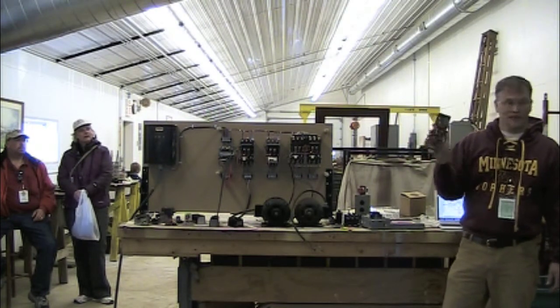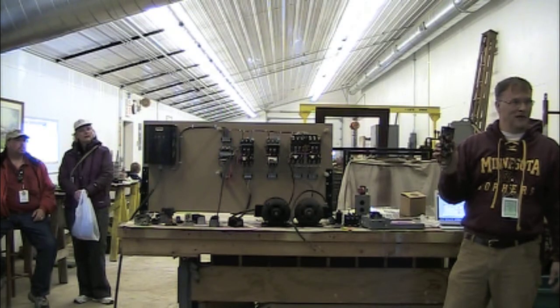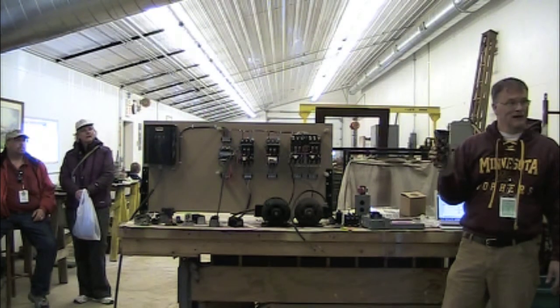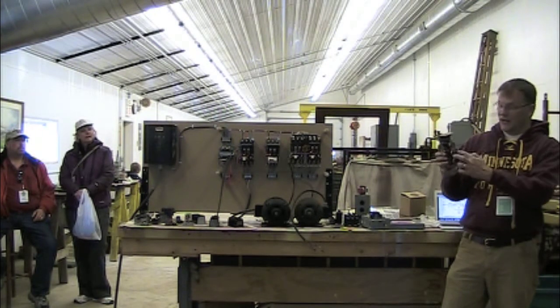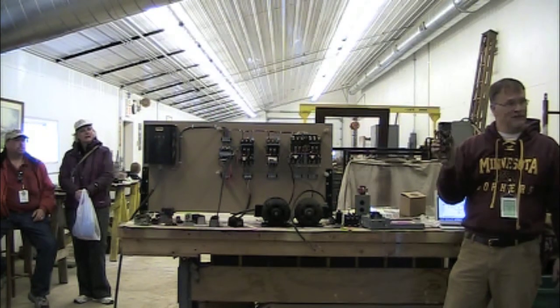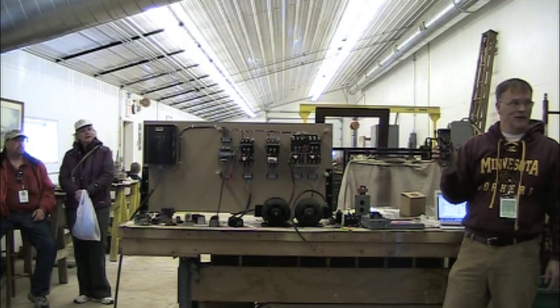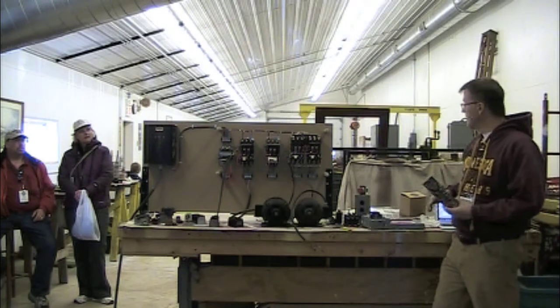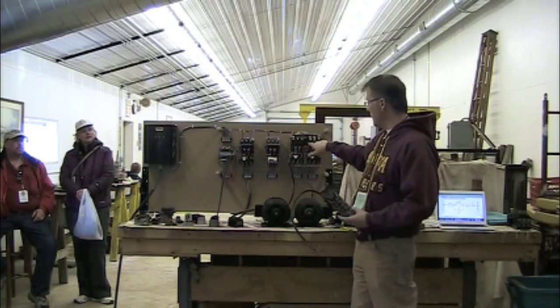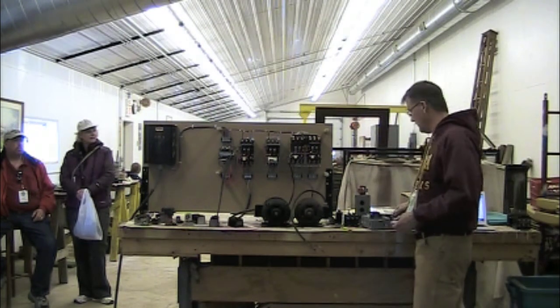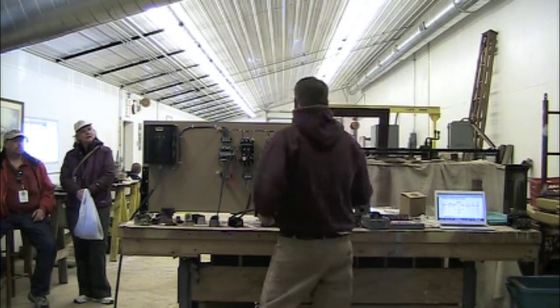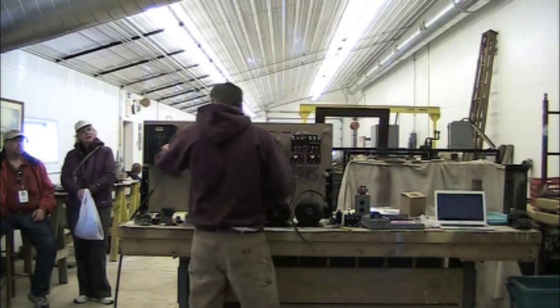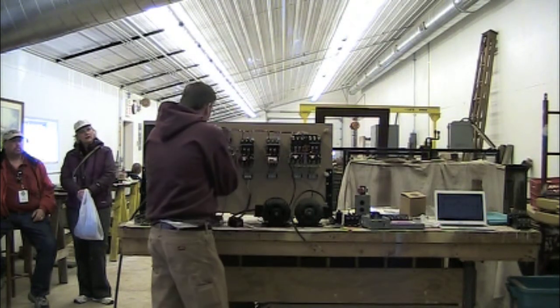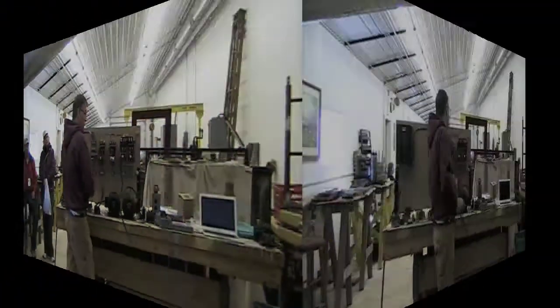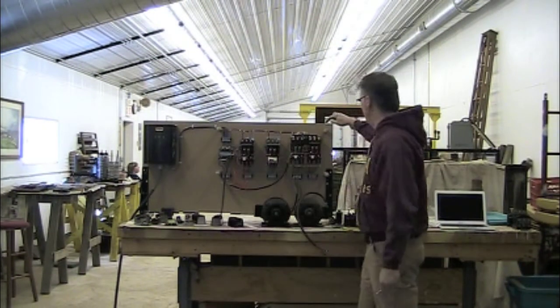But it actually, to do 2-speed now, needs a lot more logic in that control circuit. Each of the start and stops need to have a normally open and a normally closed. And they're all getting wired up into the various pieces. I was going to wire this one up. My 2-speed is going to be 2 motors. Well, okay, the one thing I didn't finish on this one.